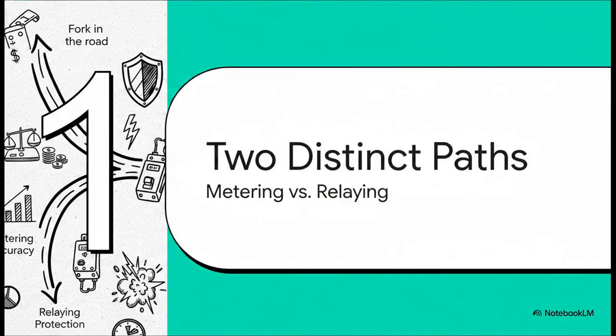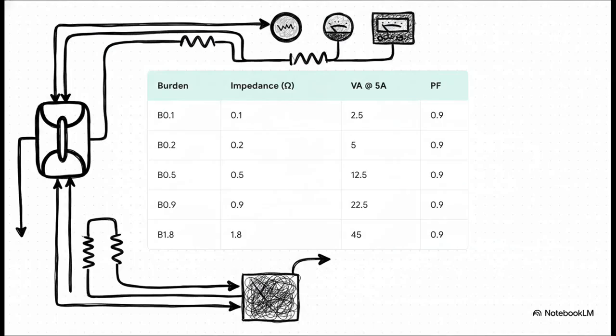Moving on to Section 2, two distinct paths: metering accuracy versus relaying protection. We've officially reached a fork in the road here because current transformers really serve two totally different masters. On one hand, we need incredibly precise accuracy for revenue metering, right? Because that's literally how power gets billed and tracked. But on the other hand, we need rugged, unflinching durability for relay protection during massive, unpredictable electrical faults. So let's explore that metering path first.